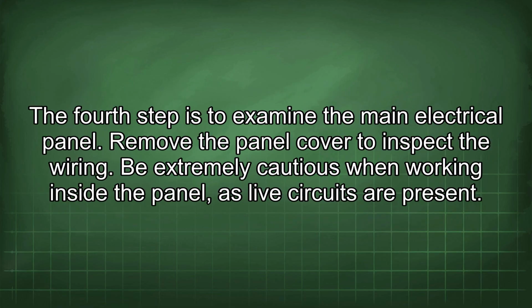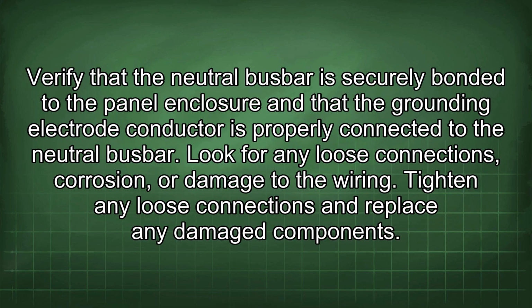The fourth step is to examine the main electrical panel. Remove the panel cover to inspect the wiring. Be extremely cautious when working inside the panel, as live circuits are present. Verify that the neutral busbar is securely bonded to the panel enclosure and that the grounding electrode conductor is properly connected to the neutral busbar. Look for any loose connections, corrosion, or damage to the wiring. Tighten any loose connections and replace any damaged components.